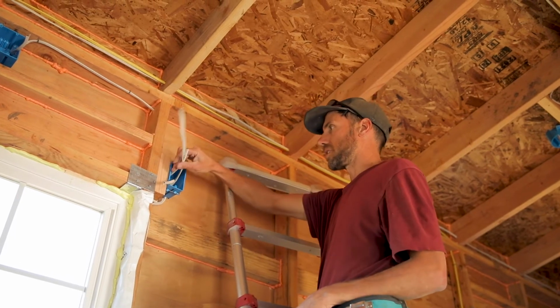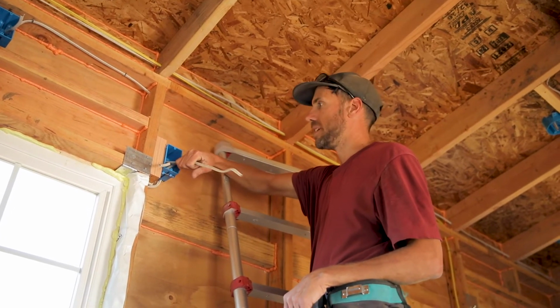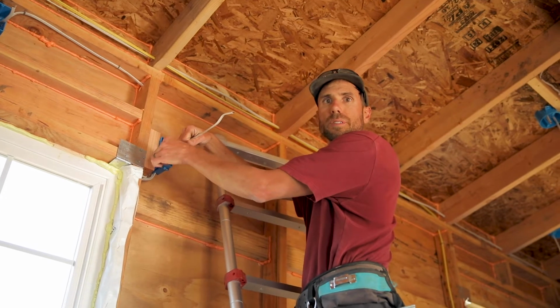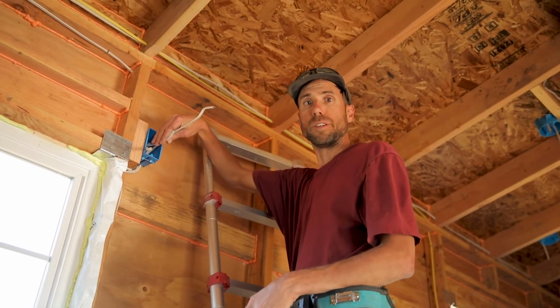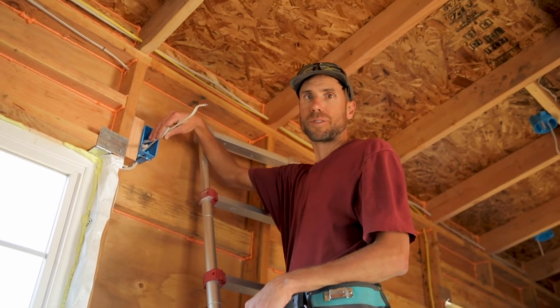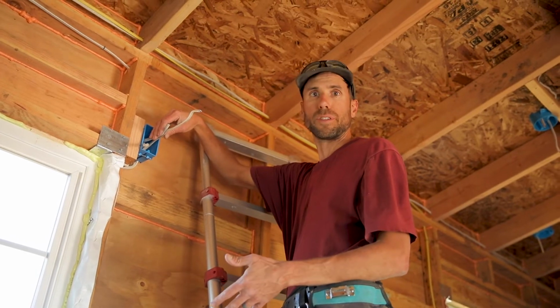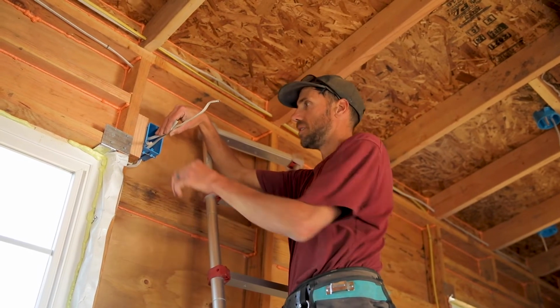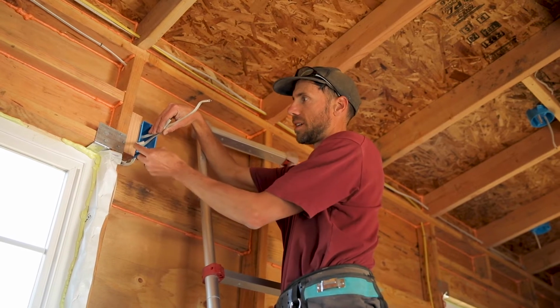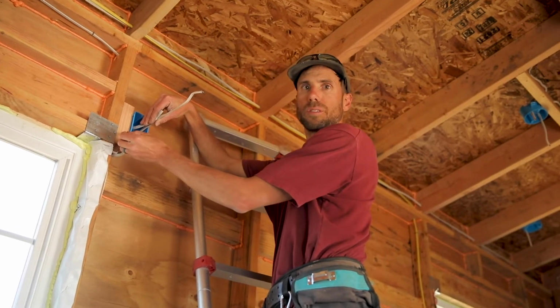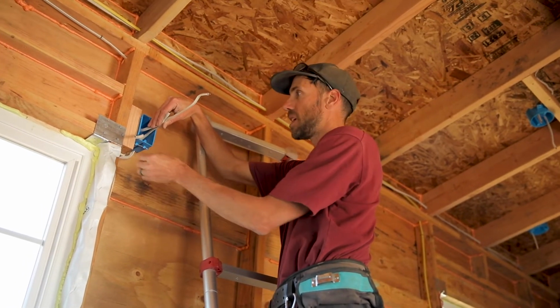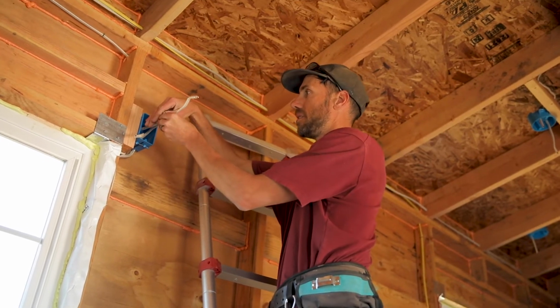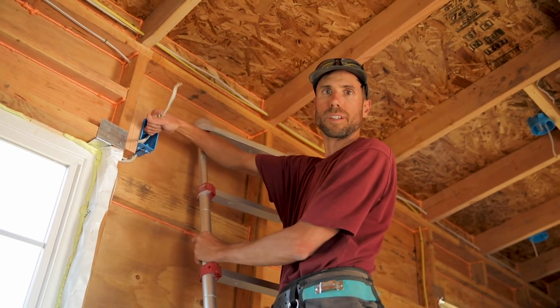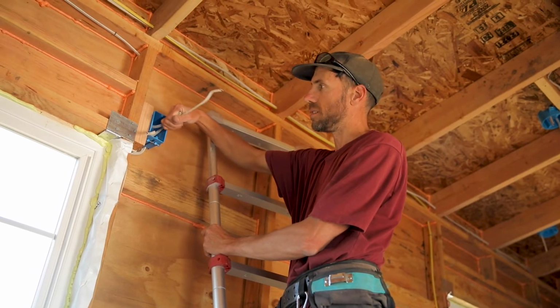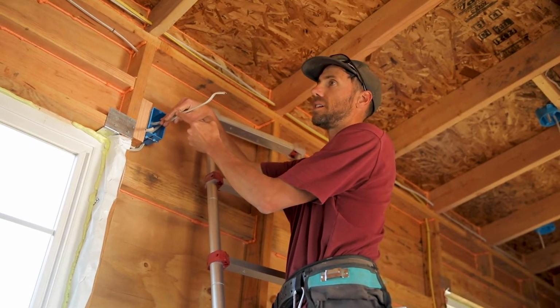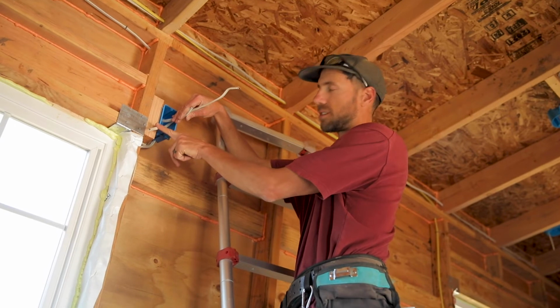So we're just going to tie these two together, and this is just our light switch. The one thing about that is when we do this, we do not tie all the neutrals together like normal, because they're two different circuits. This one is just going to stay, and we'll attach the neutral to the light bulb neutral, and these are going to get tied together. The neutrals get tied together because they're on the same circuit, but this one is our outlet circuit, and this one is our light circuit.